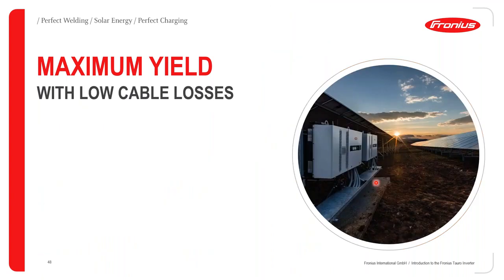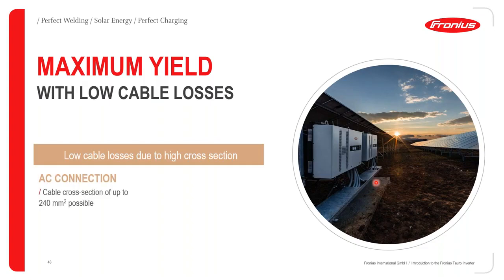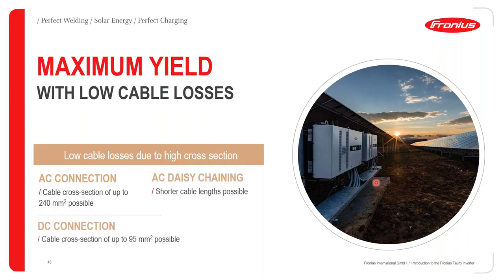Good. So after that's been said, we'll now look at maximum yield with low cable losses. As we all know, or might know, cable losses are inversely proportional to the cross-sectional area of the cable. So this invariably means that the higher the cross-sectional area of a cable, the lower the cable loss. So this is an advantage on the side of the Tauro, because we can connect up to 240 mm² cable cross-section on the AC side, and up to 95 mm² of cable connection cross-section on the DC side. And of course, with the AC daisy chaining, shorter cable is used in interconnection, and this also contributes to lower cable losses.